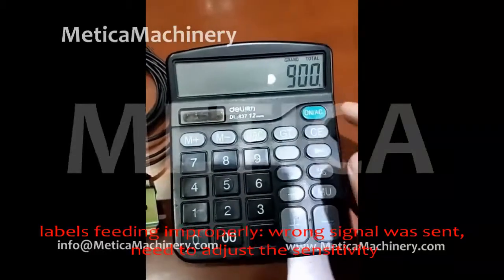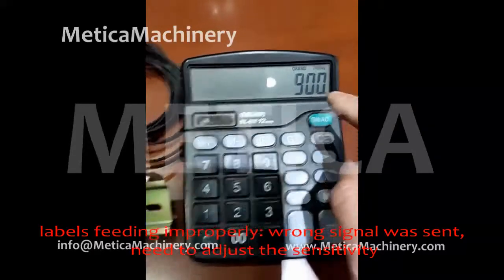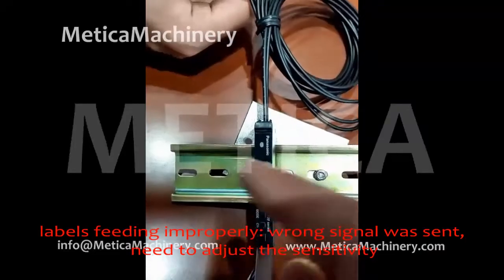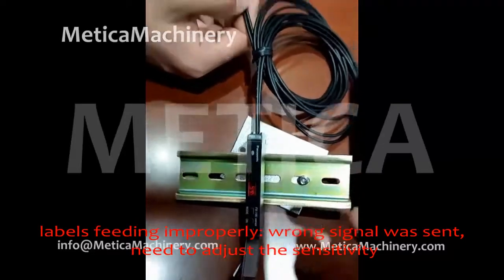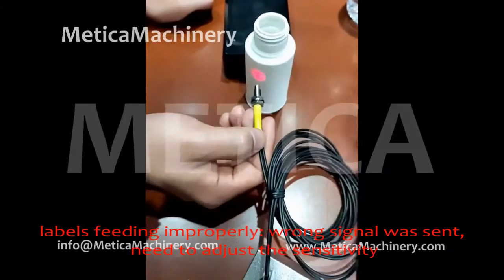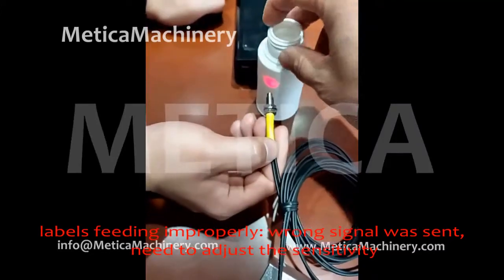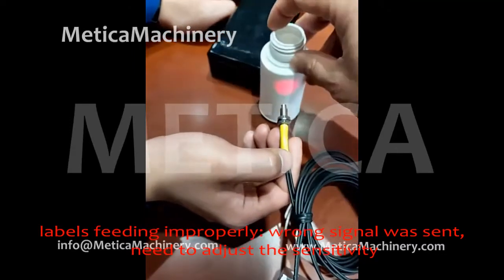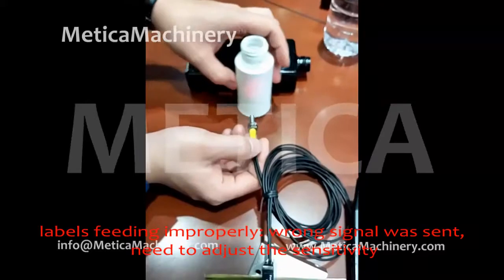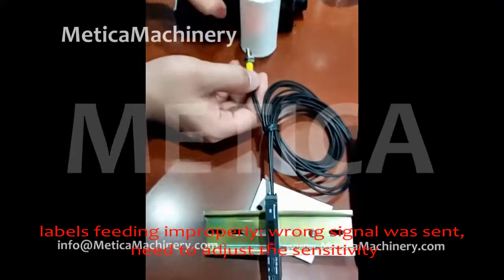We need to increase this number a little bit. It should be around 900, but we can increase it to 1000 or even 1100 to decrease the sensitivity a little bit, to avoid getting more than one signal per bottle.